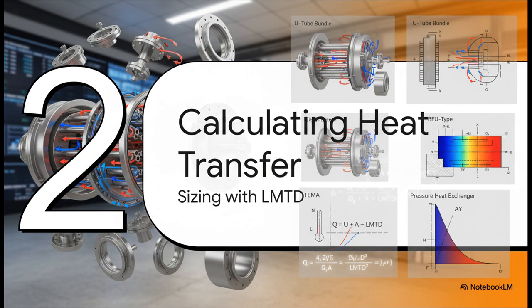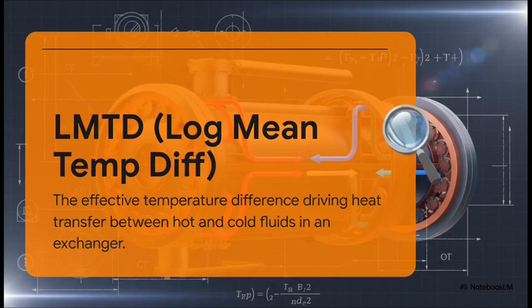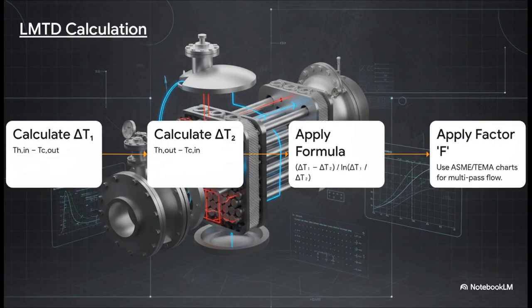Now the big question is, how big does this thing actually need to be? To answer that, we've got to calculate the total heat transfer area we need. One of the biggest challenges here is that the temperature difference between your hot and cold fluids isn't constant. It's always changing as the fluids flow through the exchanger. So how on earth do we get a single, usable number to work with? Well, that is exactly where the log mean temperature difference, or LMTD, comes into play. It's basically a special kind of average that gives us the true driving force for heat transfer across the entire unit.